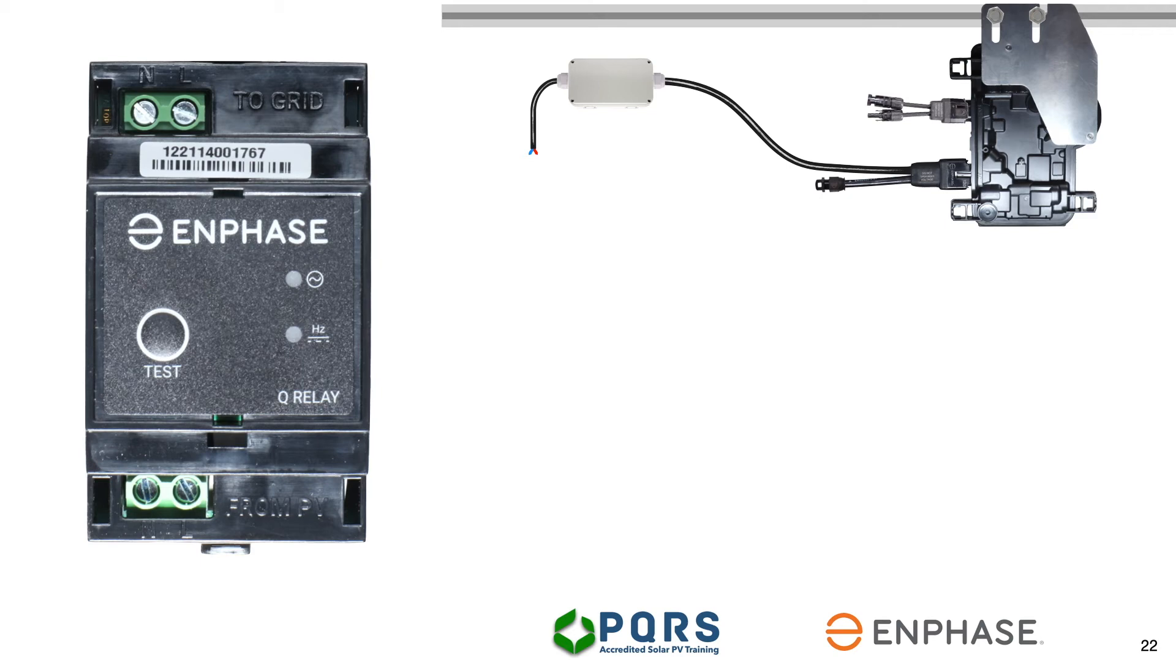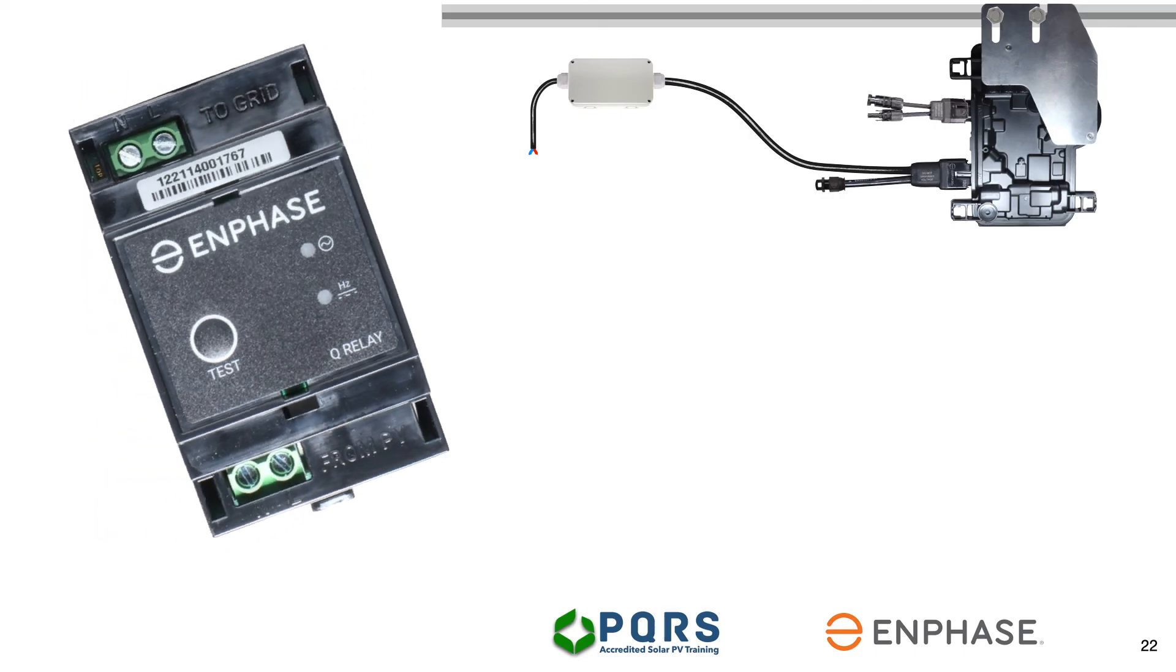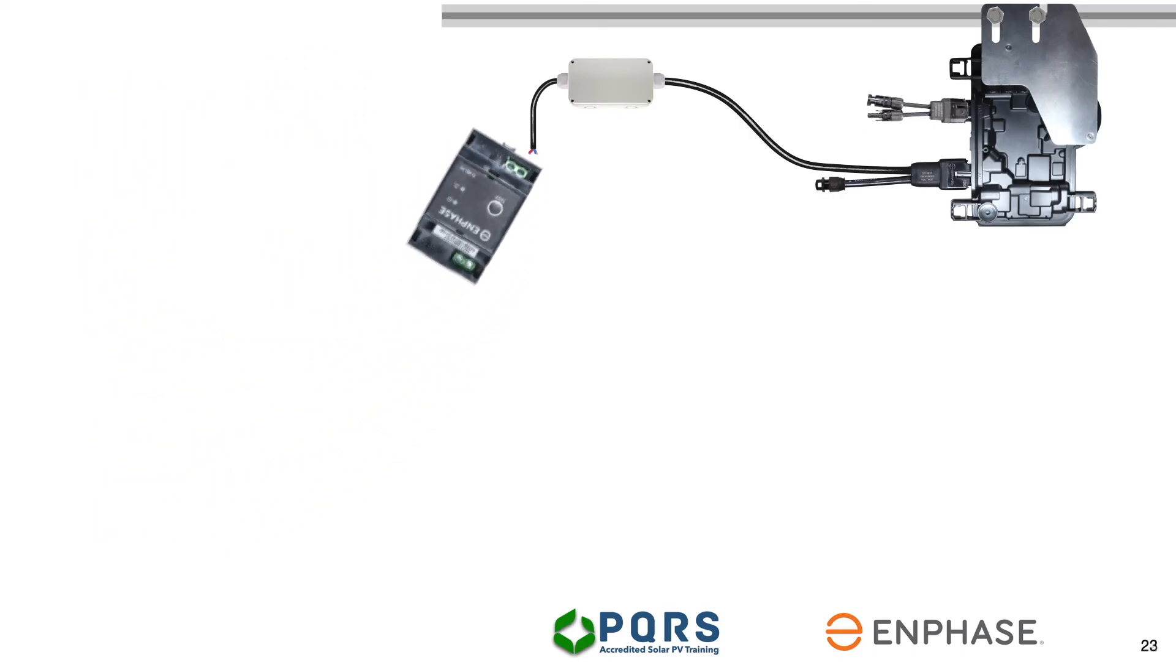Looking at the Q-relay, we see the two grid and from PV embossed on the unit. In order to safeguard the Q-relay and conductors, we need to fit a 20-amp two-pole circuit breaker.